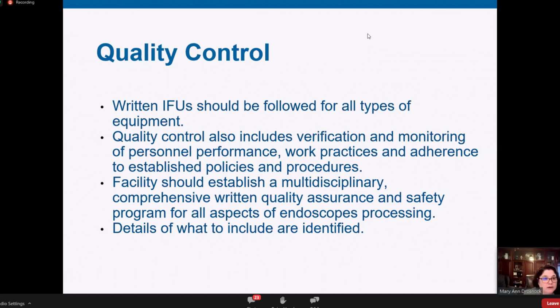Now, all we had traditionally was the test strips that show that the disinfectant is above the minimum recommended or minimum effective concentration. But other than that, what else did we have? So now with ST91, we see a lot more engineering of quality parameters in there. So we have done our cleaning. We're testing that we've done our cleaning by using a cleaning verification test. We're inspecting the scope externally, internally.